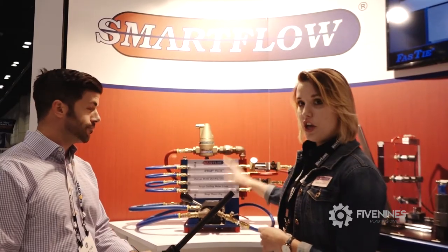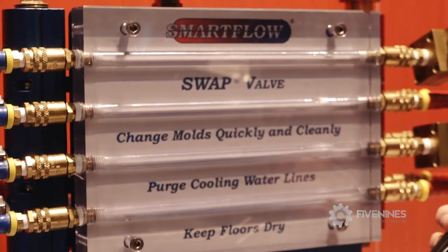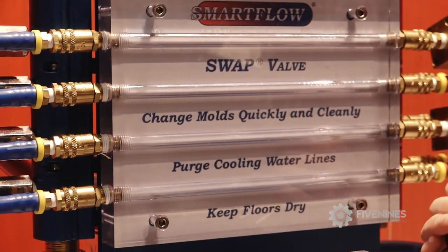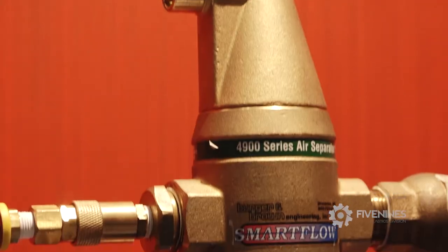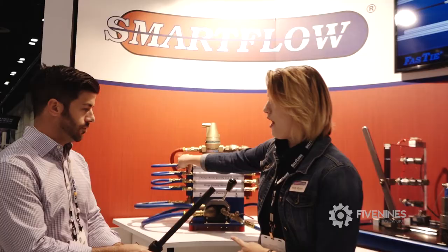Whenever you're ready to change your tool, to do it quicker and cleaner, you can switch the SWAP valve over to air and it's going to purge all the water out of the mold. The air is coming in through this pipe here and it's coming out through our air separator. Then you'll put it over to vent once it's off and you can take off each line.